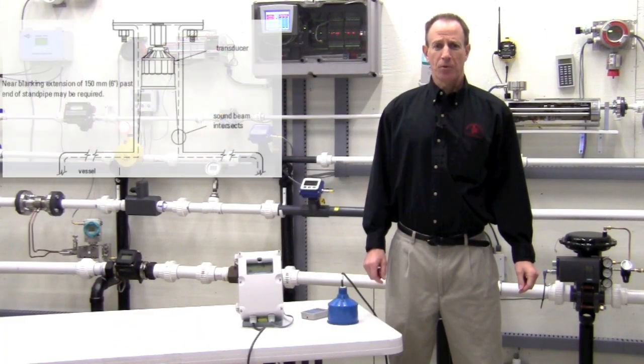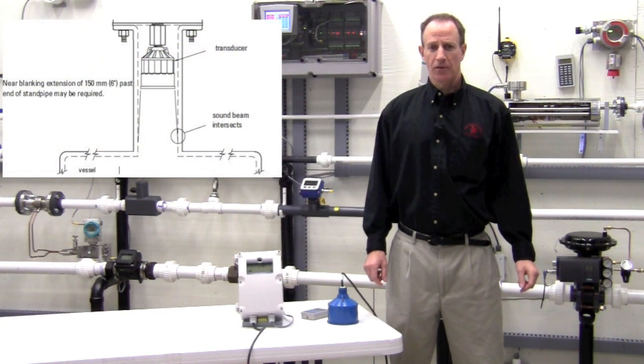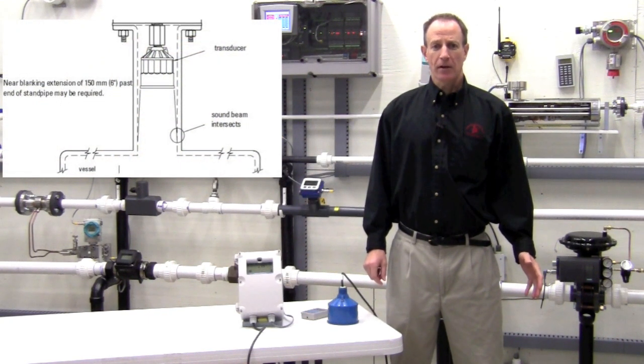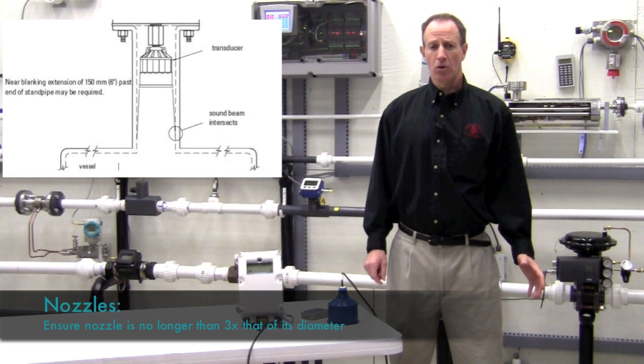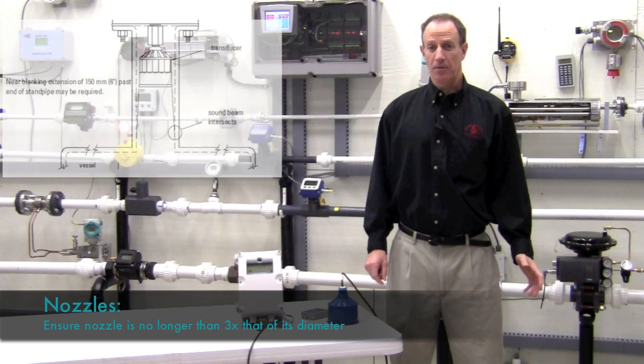Nozzles can create problems for both threaded and flange sensors. A nozzle may make the reading look higher than the actual level. Siemens suggests that any mounting nozzle length would be no longer than three times the nozzle diameter.